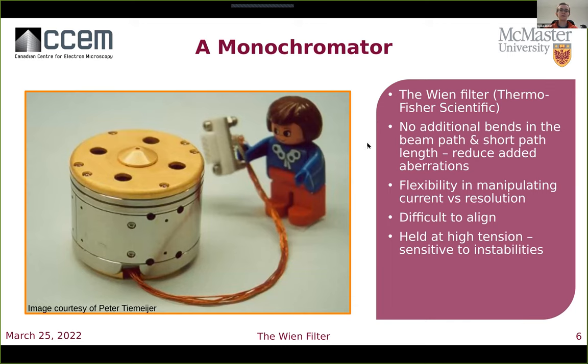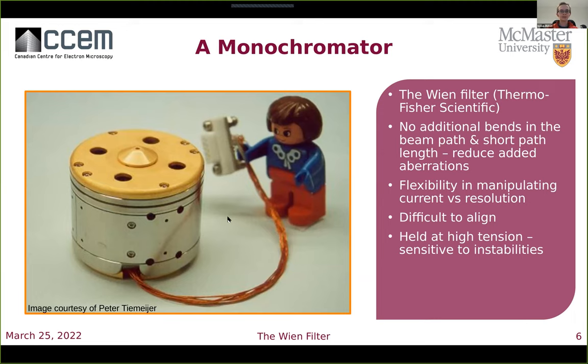I'm going to focus on one particular monochromator, the Wien filter that the Titan microscopes are equipped with. The Wien filter is quite a short monochromator and requires no bending of the electron beam, which travels in a straight path. This was designed to reduce the aberrations that having a monochromator can introduce. This filter provides a lot of flexibility in choosing the balance between current and energy resolution, but this flexibility comes with the cost that it can be quite difficult to align. This monochromator is also held at high tension and can be very sensitive to instabilities in the high tension supply, meaning the user may observe the mono drifting a lot and have to keep correcting for that drift.